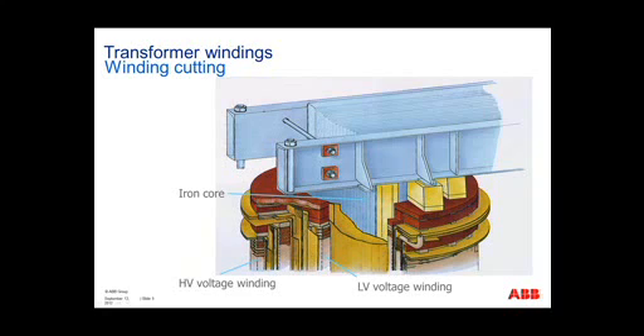If you have sufficient cooling on your transformer, your voltage can actually rise. You have different set points that the transformer manufacturer will provide to you of what your limits are, and that is in the documentation of the transformer. So you have different factors you have to account for: if you have external cooling, how good your oil is, how old the transformer is. These variables are all considered when you set your overvoltage relays, which is documented in the manual of the transformer provided to you.